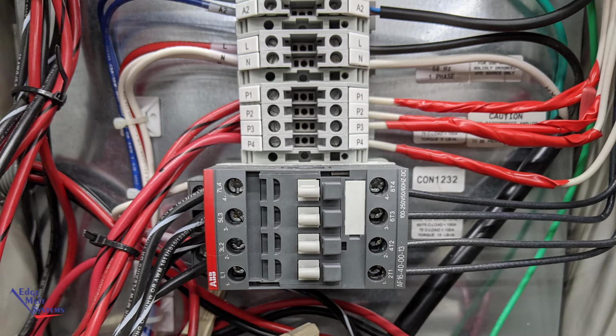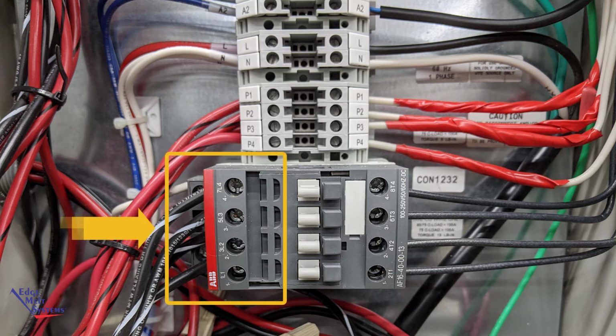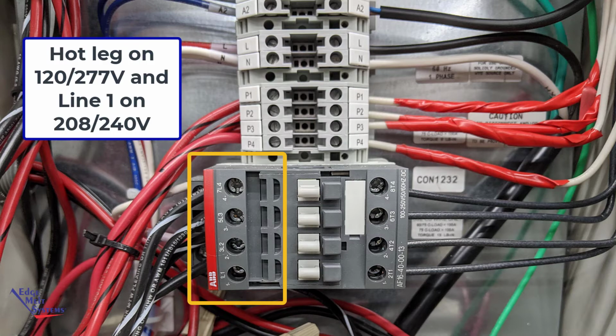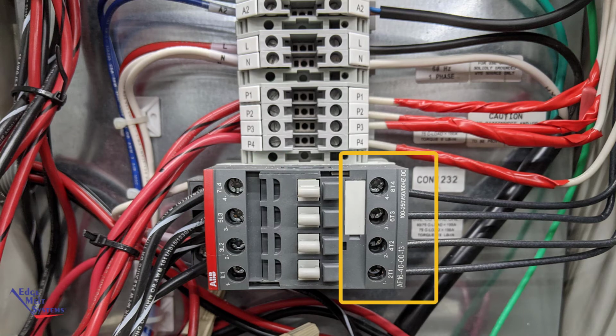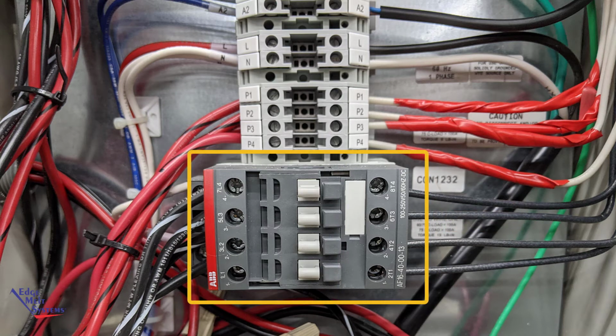Again, demonstrating the 4 EPD units coming in through the ABB contactor. The load side again is indicated by the stripe wire of leg 1, the hot leg on 120 volt and 277, as well as leg 1 of 208 and 240 are run into the left side of the ABB contactor, and then the load coming out on the right side out to the heat cables. Again, this is demonstrating for 4 circuits. This controller can be used for 1 through 4 circuits, but this shows it with all 4 circuits being used.